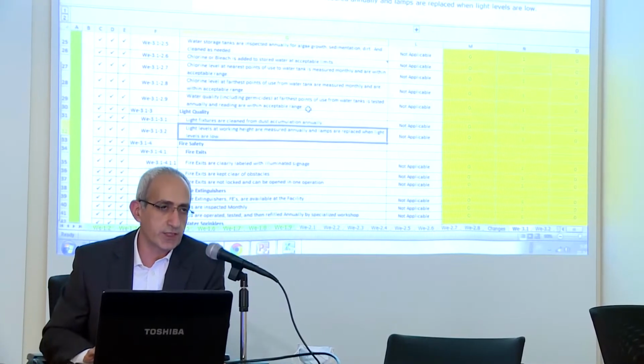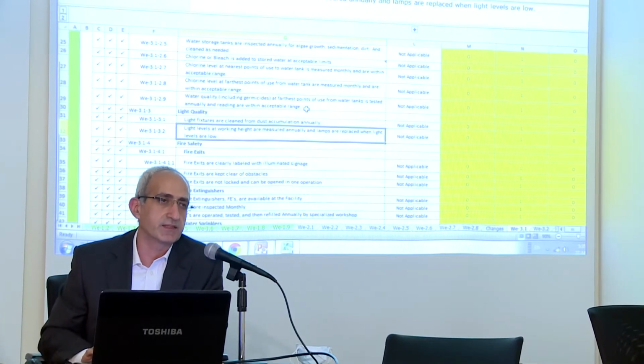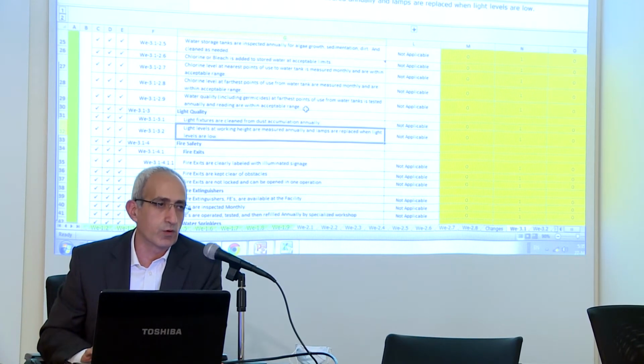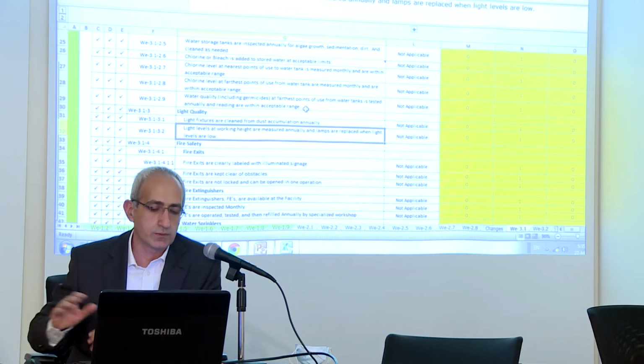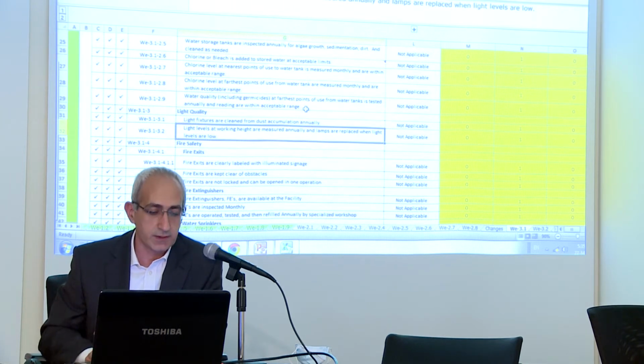So now we come to light control, light quality. Here we ask that the light fixtures are cleaned in a regular manner, and annually the light levels are rechecked, and relamping is activated in case there is a low level, not waiting for the lamp to burn out completely to replace it. And the frequency is annual, so I think it's a fair frequency.